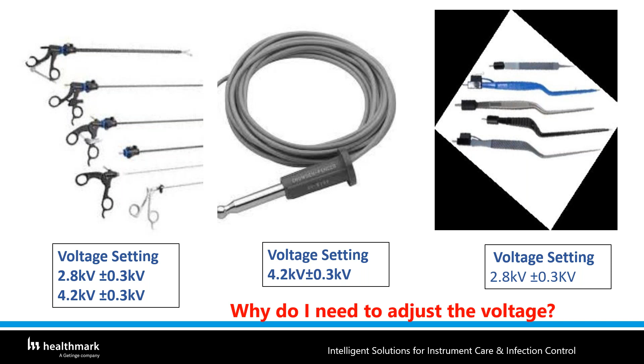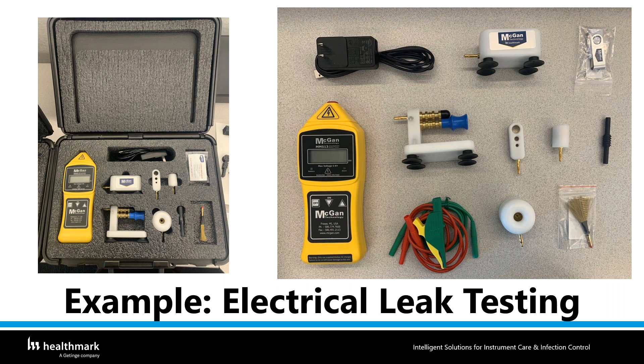So we have, for example, this high voltage tester that you can actually use to test for those issues. And we found out that some of the monopolar and bipolar instruments require different levels of energy. So when you select one of these, you want to make sure you have one that goes to, say, 1000 volts, versus, for example, something with a thick coat where you want more than 4000, 4200 volts to be able to detect faults in those insulations.